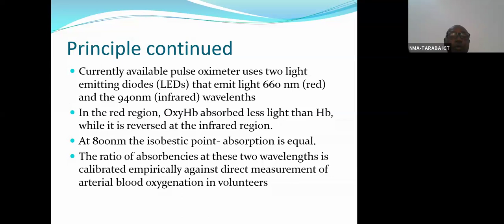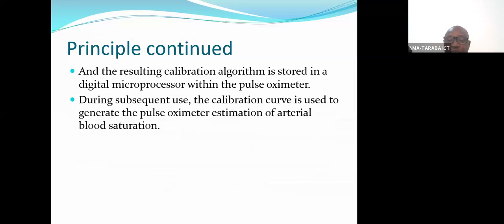So the ratio of absorbance at these two wavelengths is calibrated empirically against direct measurement of arterial blood oxygenation in volunteers. And this is what is recorded in the pulse oximeter that will give you the reading. The resulting calibration algorithm is stored in a digital microprocessor within the pulse oximeter. So during subsequent use, the calibration curve is used to generate the pulse oximeter estimation of arterial blood saturation.